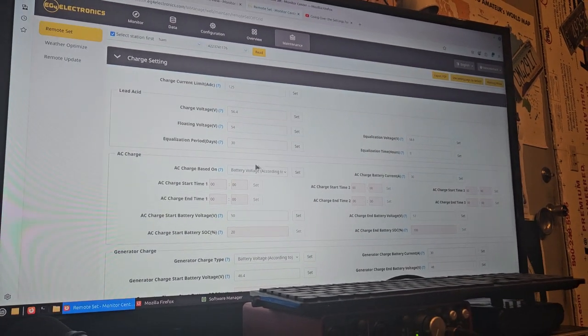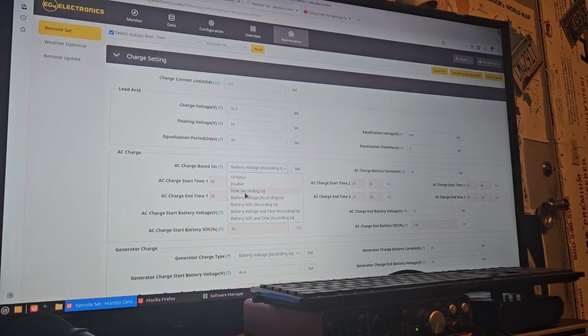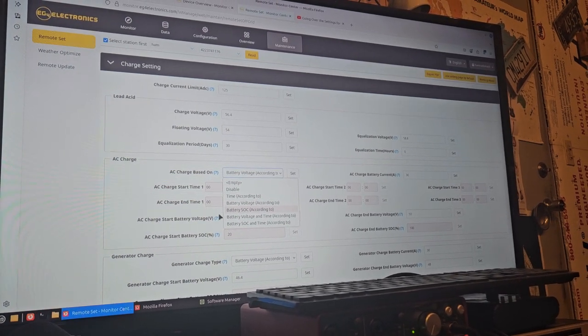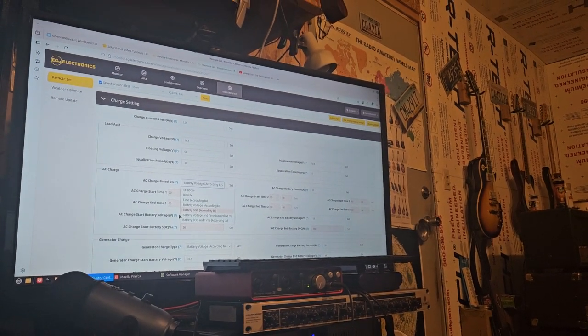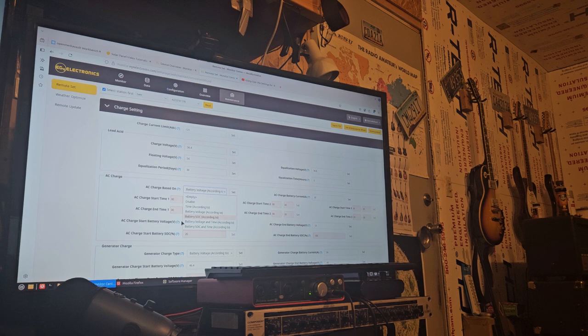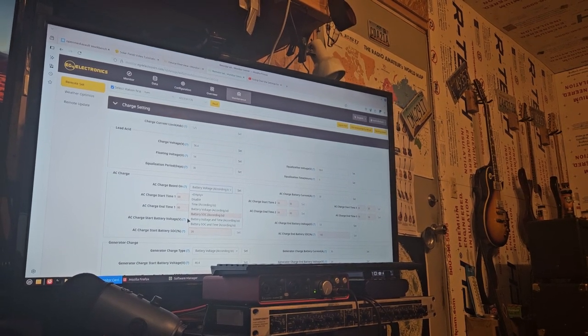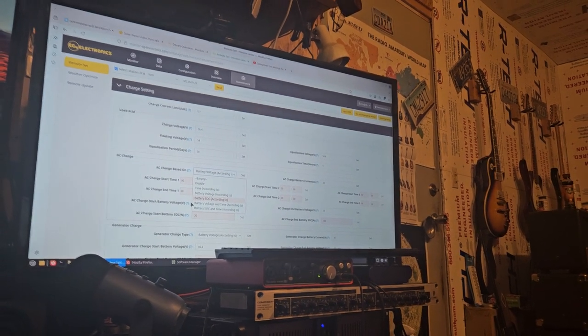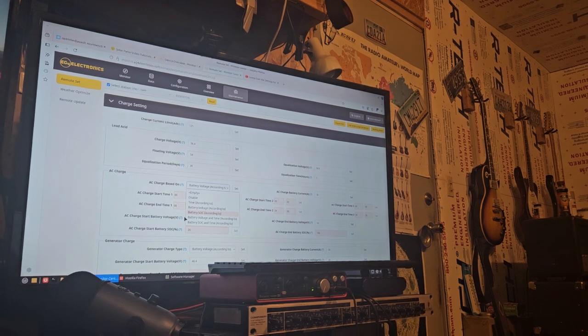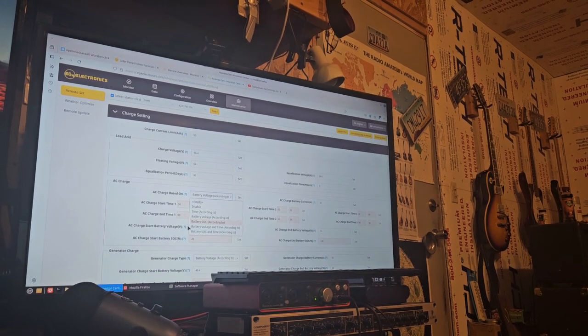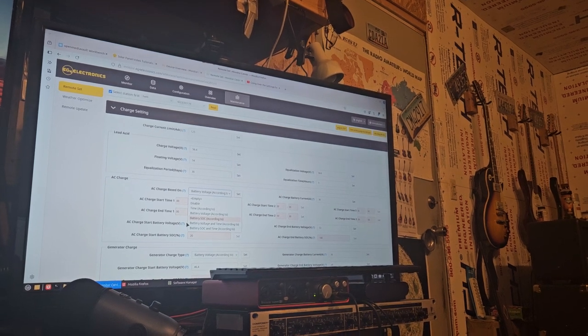AC charge is based on whatever you want to select - disable time, battery voltage. You could have this thing act basically like a UPS, and say, well, my off-peak hours are, let's say, 7 or 8 p.m. to 3 p.m. in the afternoon. Peak hours here are usually 3 to 7, or 3 to 8, or 2 to 8. So you could have this set to continually be charged and ready to use at those times.